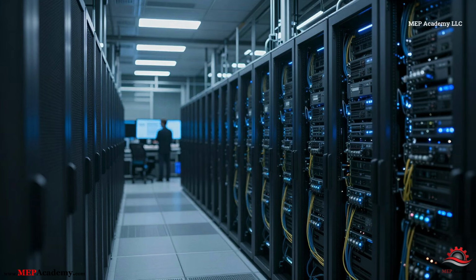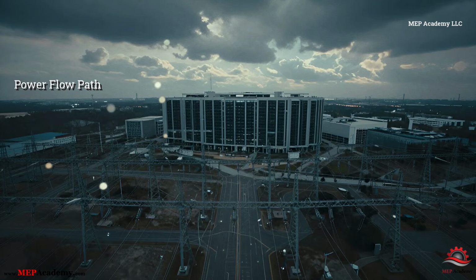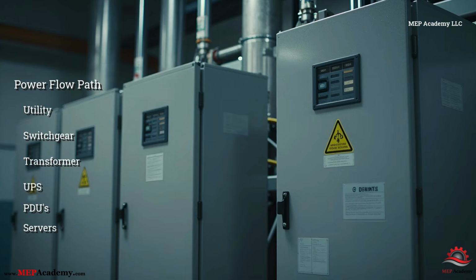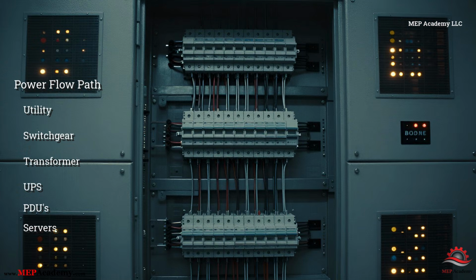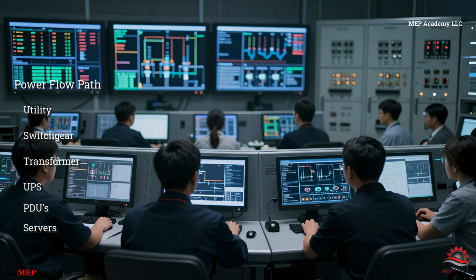Let's start with the first concept. Data centers use specialized electrical distribution systems that are built to handle enormous and constant power demand. Inside a large data center, electricity arrives from the utility grid at medium or high voltage, often between about 13,000 and 35,000 volts. This high-voltage power enters the facility through electrical service equipment and then passes into switchgear. Switchgear is one of the most important pieces of electrical equipment in the entire building. It acts as the control center for incoming electricity. It allows operators to isolate circuits, redirect power flows, and protect the system using breakers and protective relays.